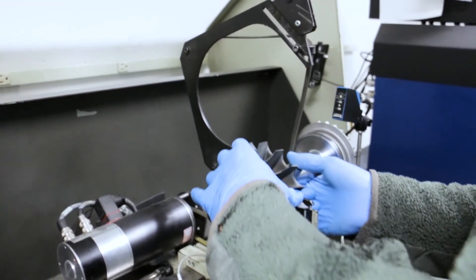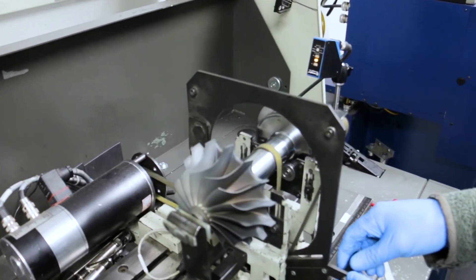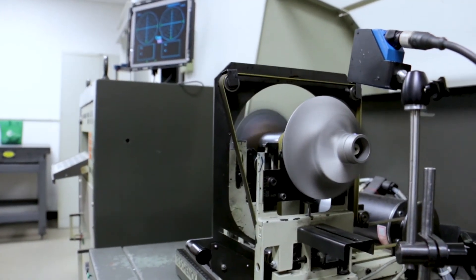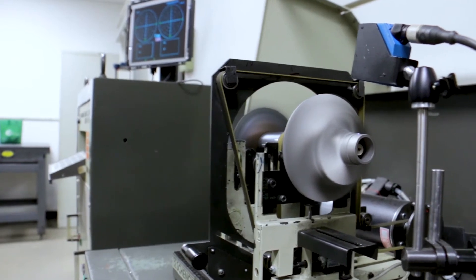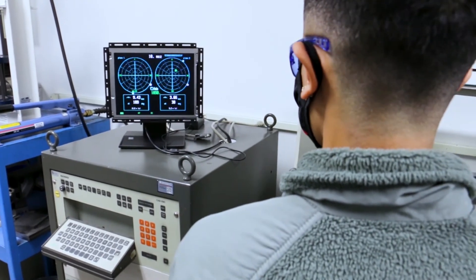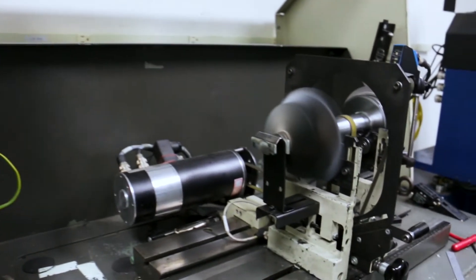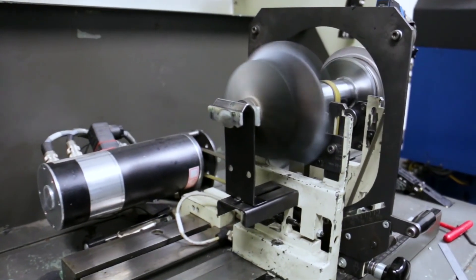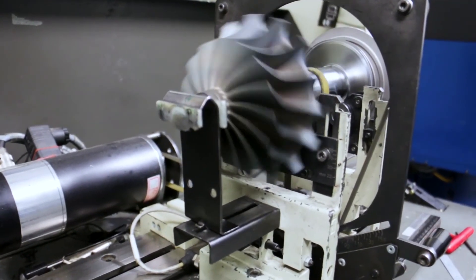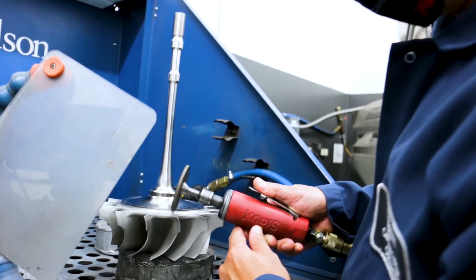When the engine is in operation at speeds of 96,000 rpm, we must ensure that the total amount of rotor displacement is minimized. Therefore, the next step of the process involves the measured removal of material to ensure the dynamic components are balanced. Our technicians measure each component's imbalance on calibrated machines, then remove any excess material until the component reaches its balance equilibrium.